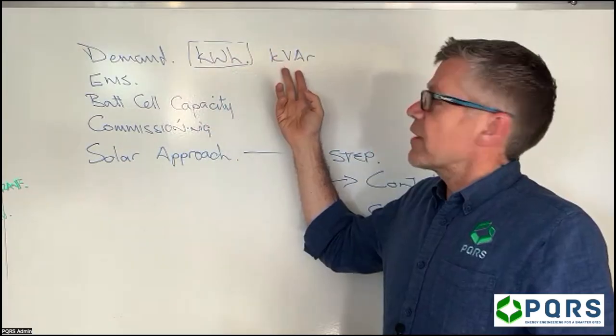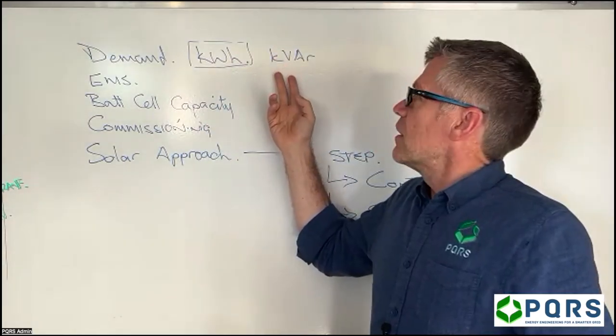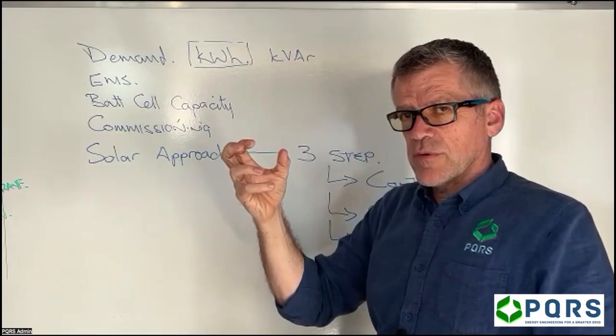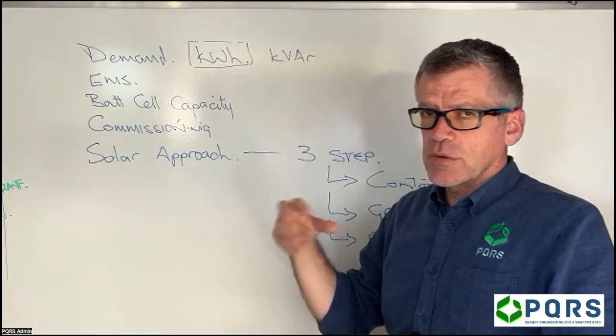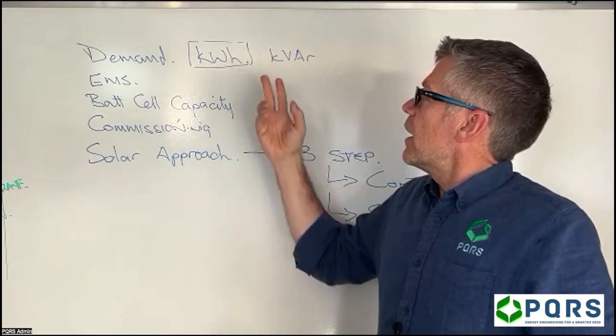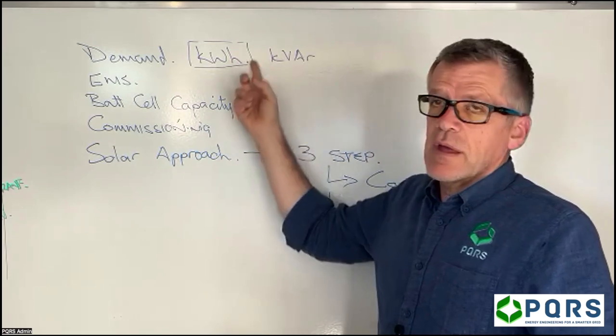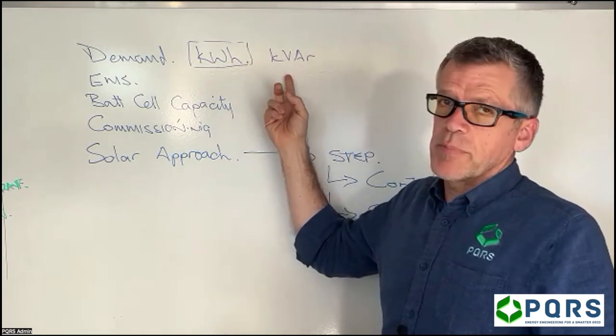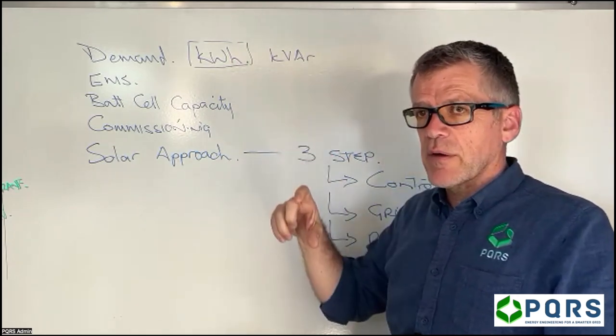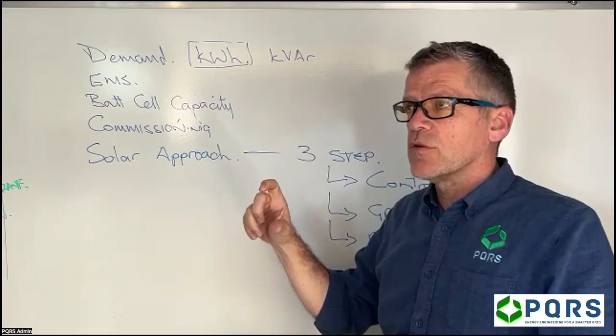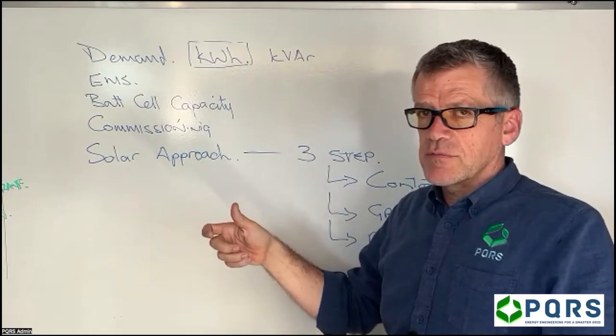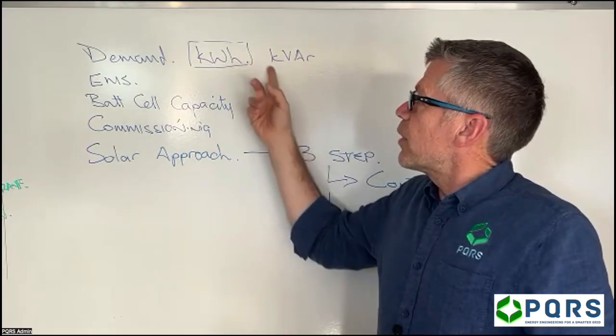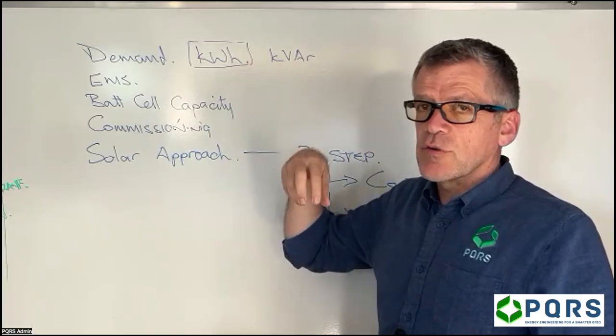Your power factor at the factory is 0.9. I took this from your metering portal and looked at your reactive power component, because reactive power doesn't change when you have a solar system fitted. It's a component created by the loads on your premises.